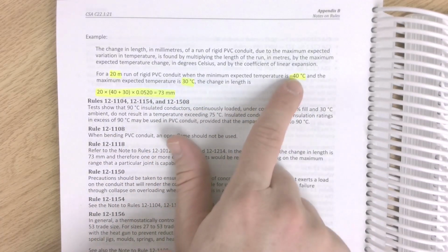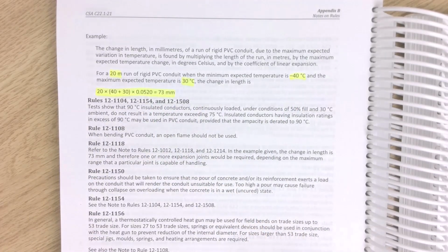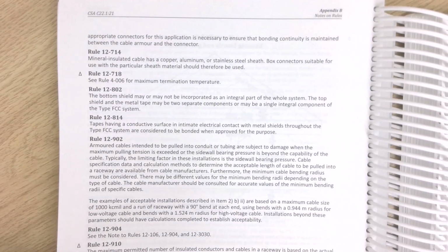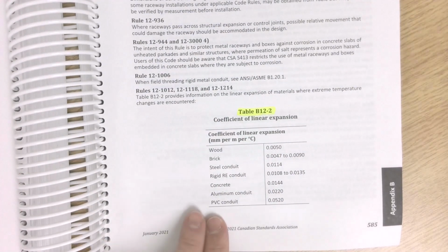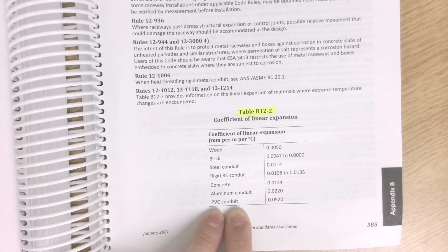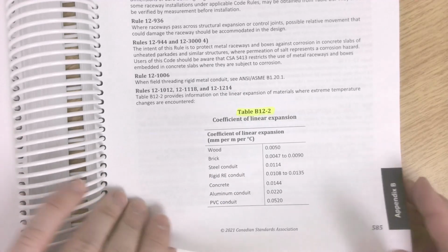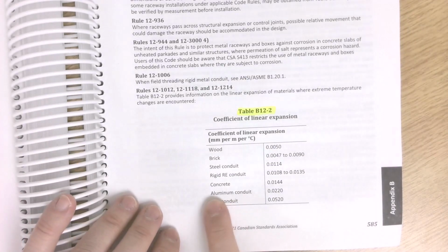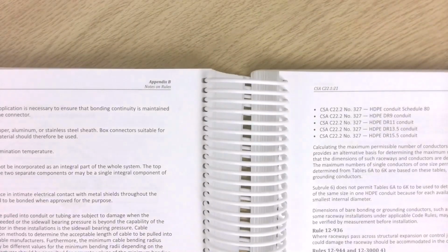So you just add those two numbers up, and then you multiply it by this temperature coefficient, or coefficient of linear expansion is actually what the code book calls it, which is on the previous page, 585. So, for example, we have a PVC conduit. There's rigid conduit. We have steel conduit, which is probably rigid metal conduit, would fall under the steel conduit category. We have aluminum conduit. All right.